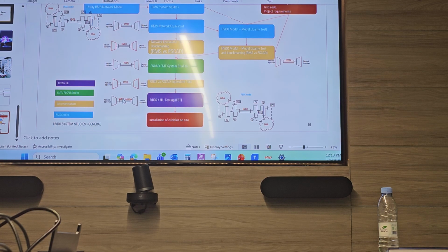It's normal, but in case of fault, this change in frequency is high, and you have an inertia. So, for example, these devices are capable of tripping immediately and blocking. So I said, no, I don't want to be blocked. I want to withstand for some time, to behave like this. So then they need to do programming. There are some curves. They say our system will behave like this. Okay, let's see. Then they will simulate all this. So there are reports in Accoms. But it's too complex to read all of this.